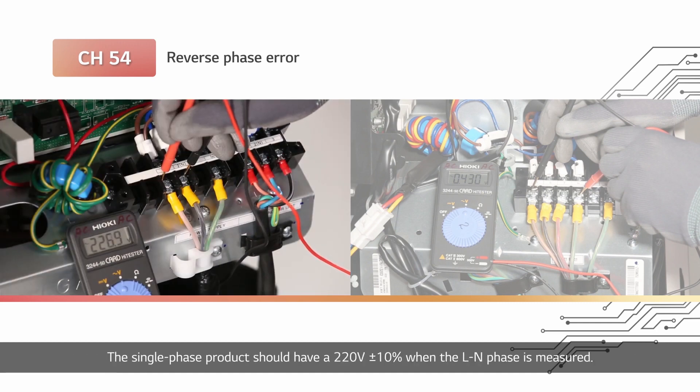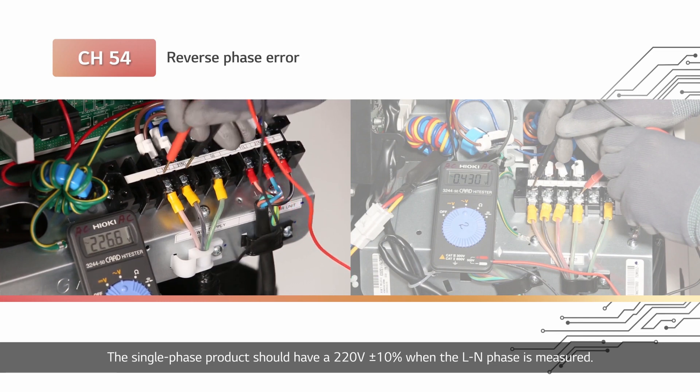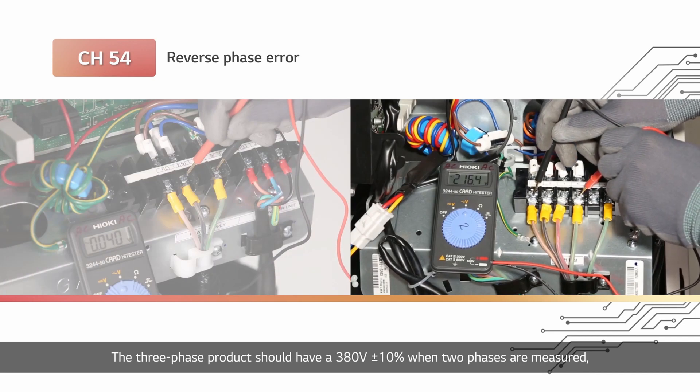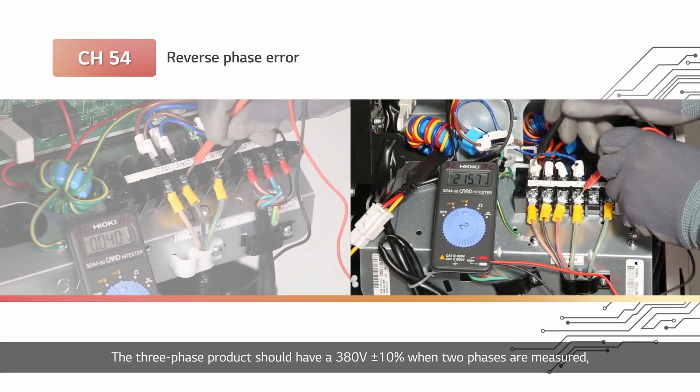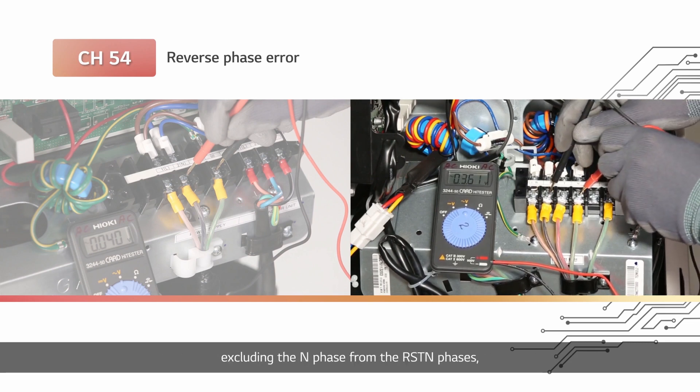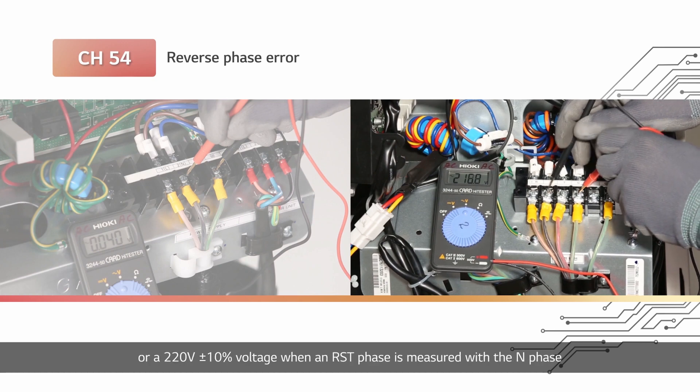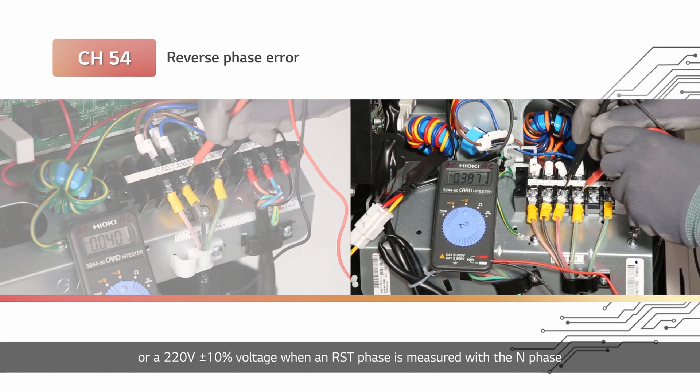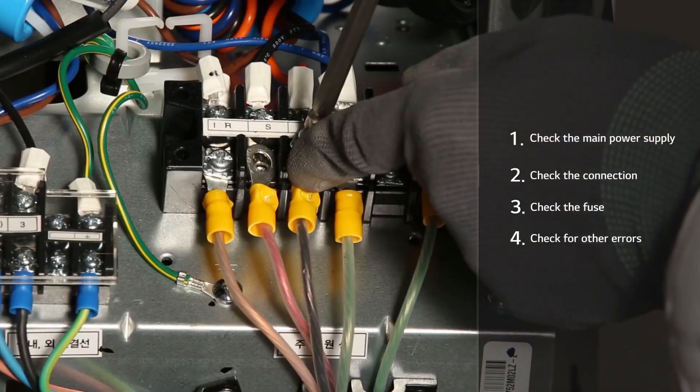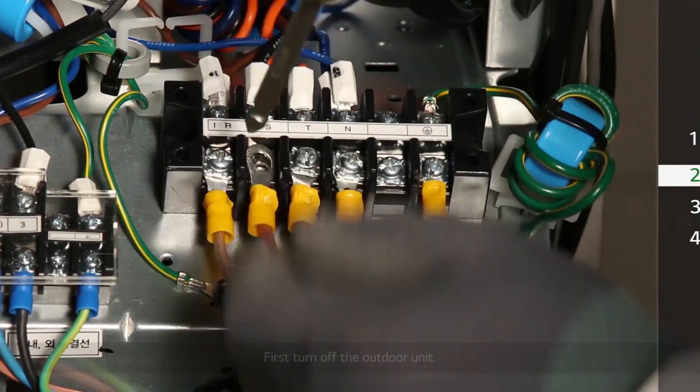The single phase product should have 220 volt ±10% when the LN phase is measured. The three-phase product should have 380 volt ±10% when two phases are measured excluding the N phase from the RST phases, or 220 volt ±10% when an RST phase is measured with the N phase.